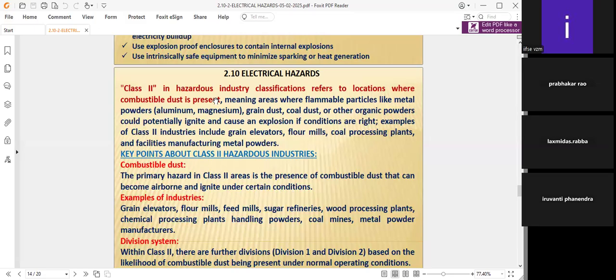in the electrical panel. That's why, where combustible dust locations are there, we mean areas where flammable particles like metal powders, aluminum, magnesium, grain dust, coal dust, or other organic powders could potentially ignite and cause an explosion when the conditions are right. Examples: class 2 industries include grain elevators, flour mills, coal processing plants, and facilities manufacturing metal powders. These are very important.